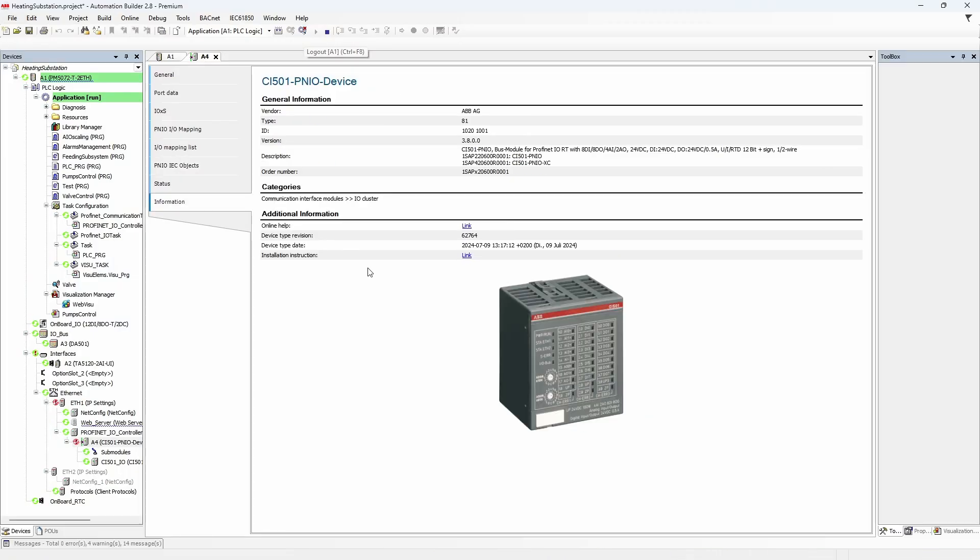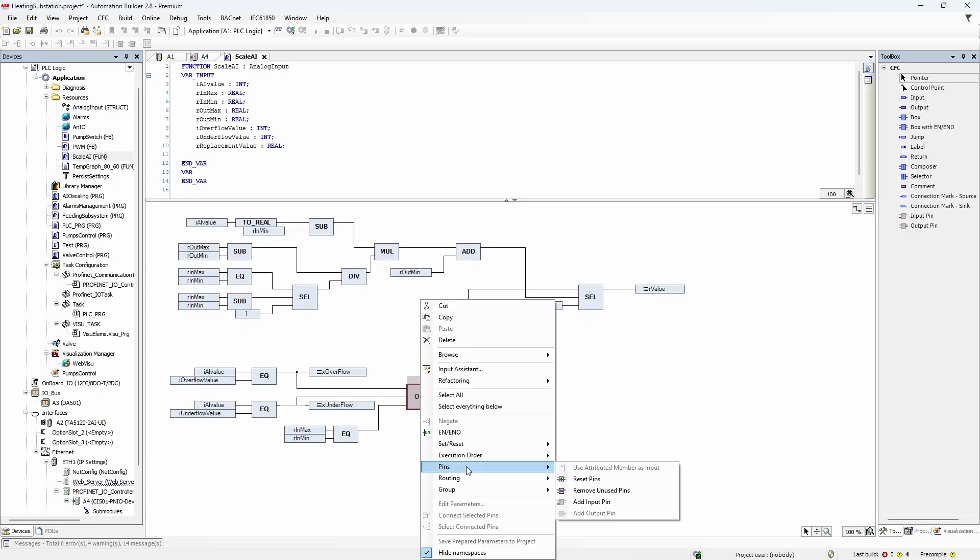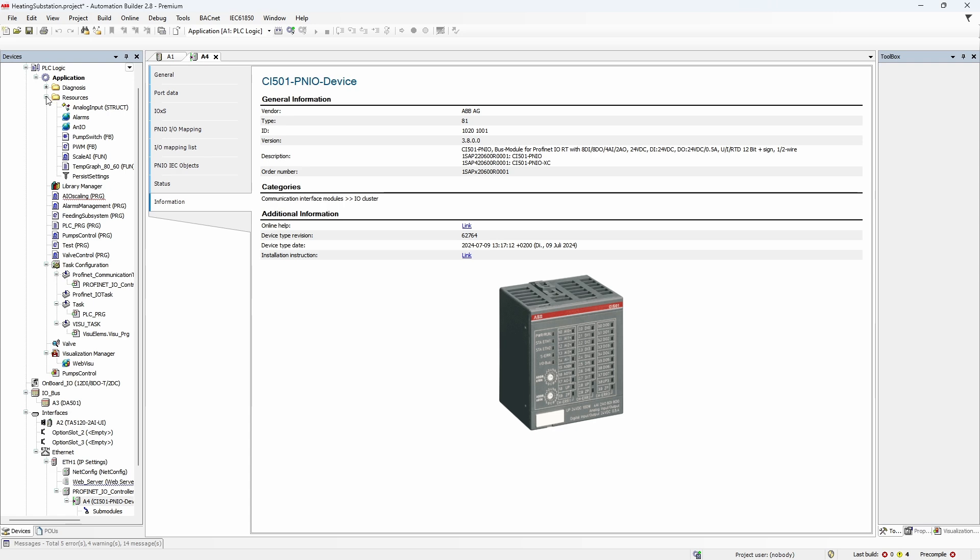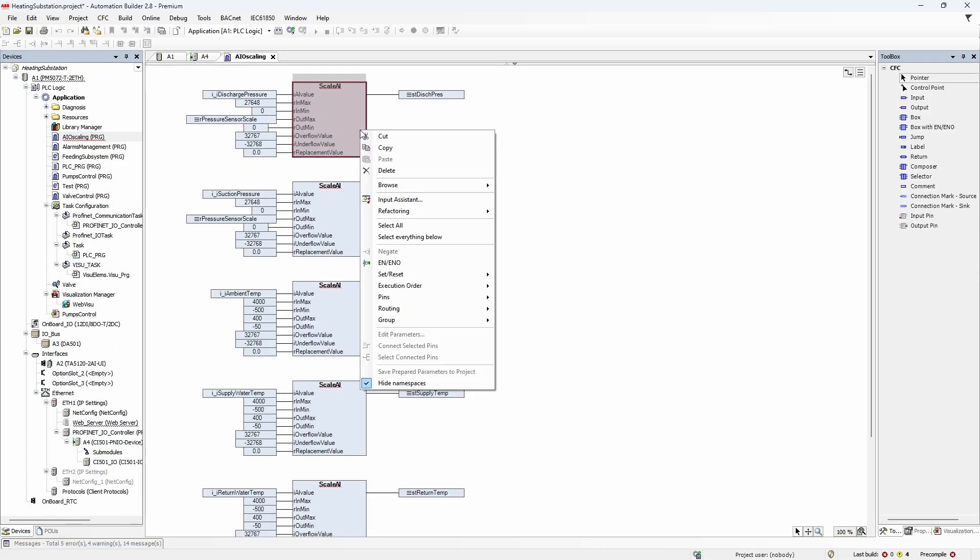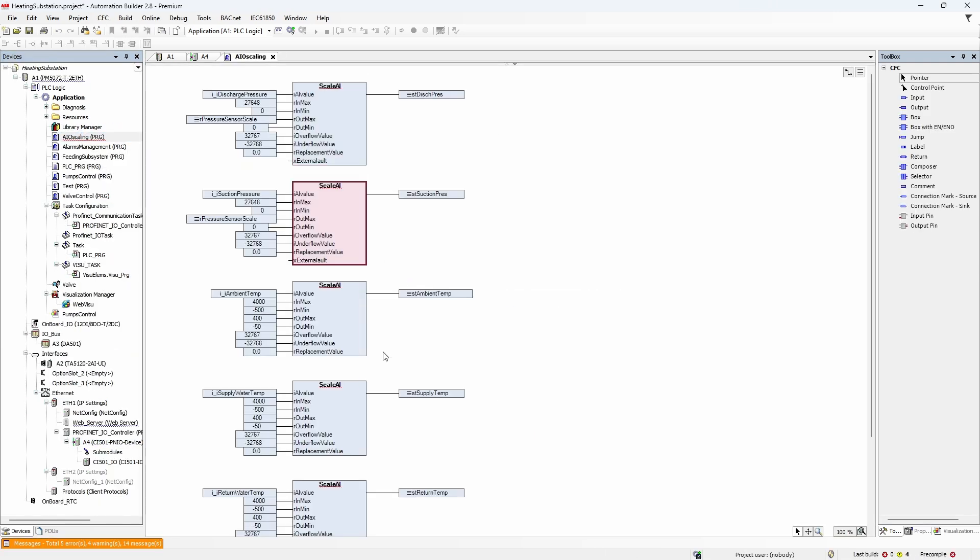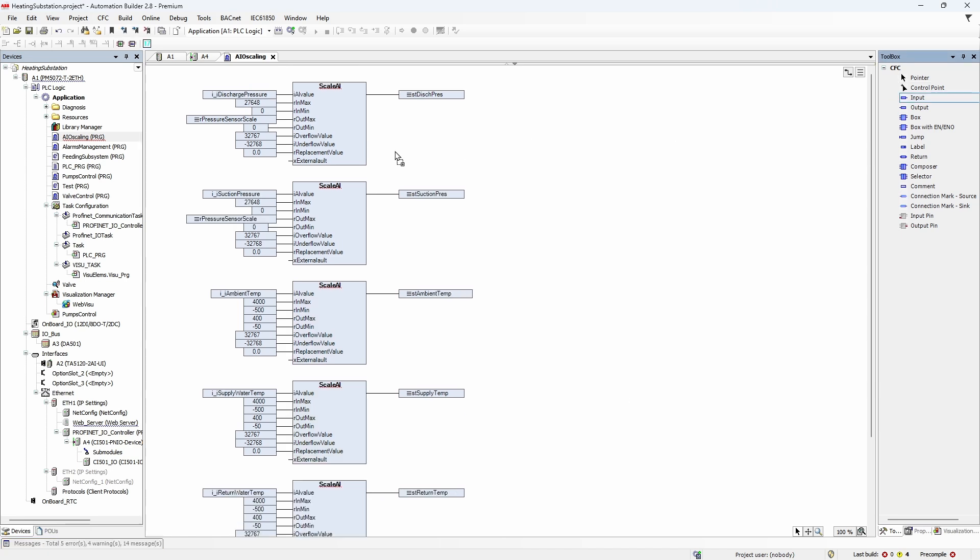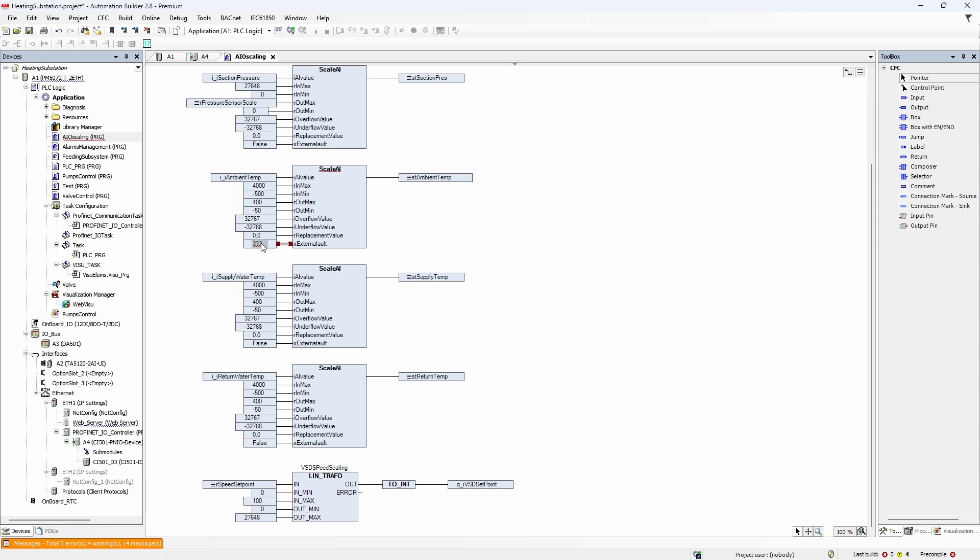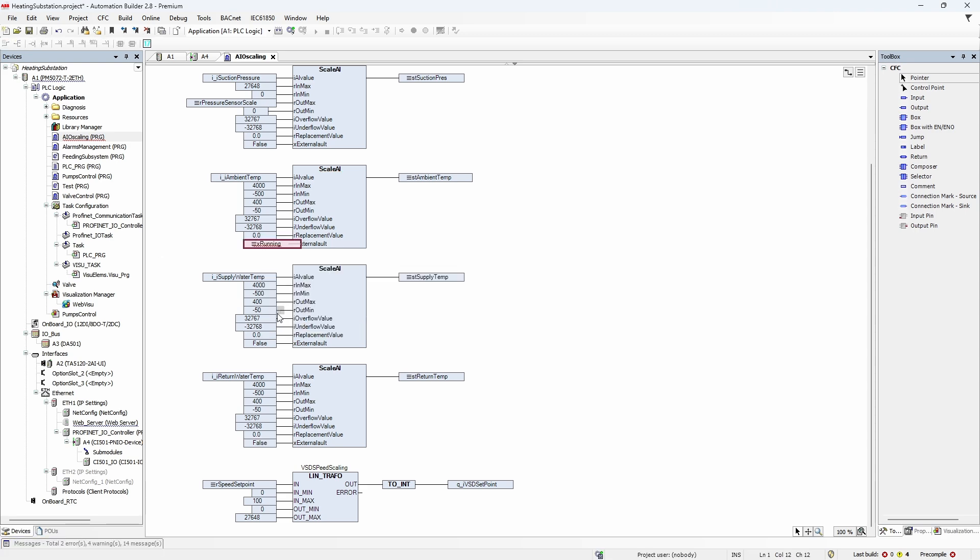Go offline, find ScaleAI function, add the additional input external fault, and then plug it in where the fault signal is formed. After that, go to AIO Scaling program and make sure function calls contain newly added input. For all local I/O inputs, connect false constant to default input. For ambient temperature, put inverted x running flag.